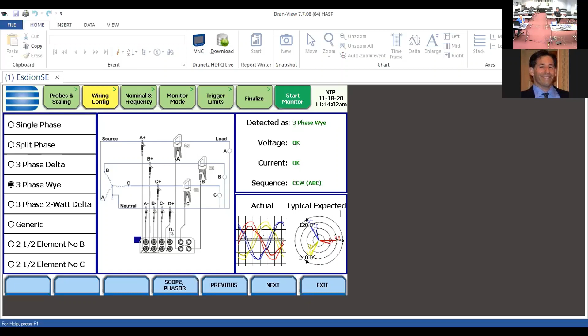The instrument will also check that you're within the voltage and current measurement range that will provide the best accuracy. For example, we see it all the time where someone uses a current probe rated for 3,000 amps but is monitoring an ampere of current. Obviously you're under ranging that current probe. The probe amplitude-wise may read 1 amp, but your phase accuracy is going to be way off, and that's going to affect other parameters like your wattage. So the instrument automatically checks to make sure you're within the measurement range, and usually your target is to be somewhere in the middle of the measurement range to have the best accuracy.